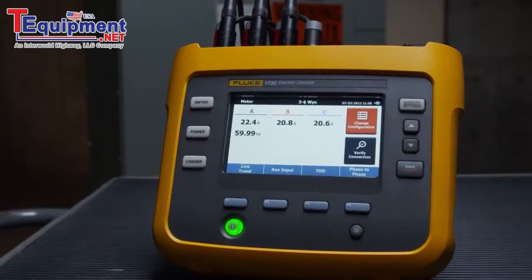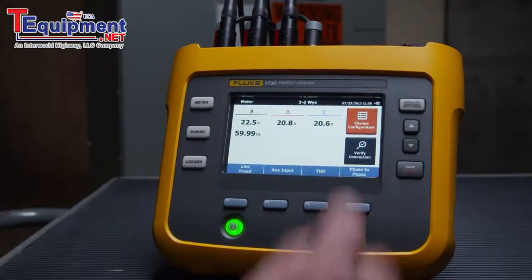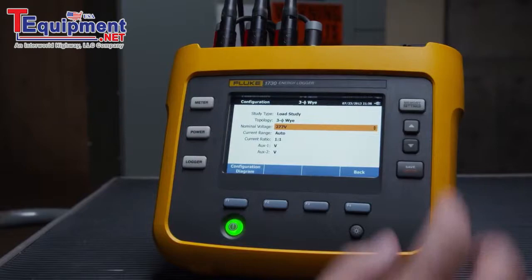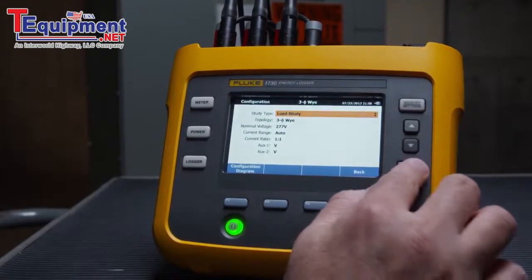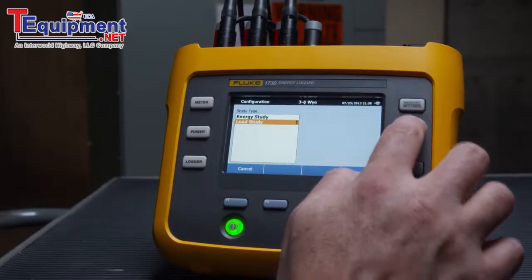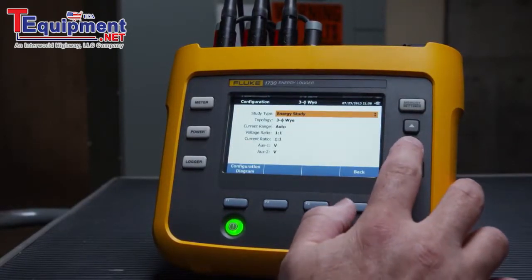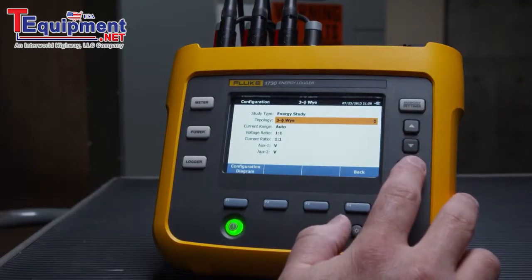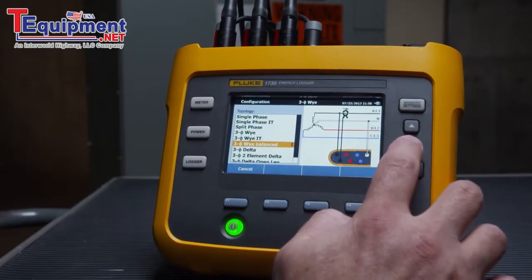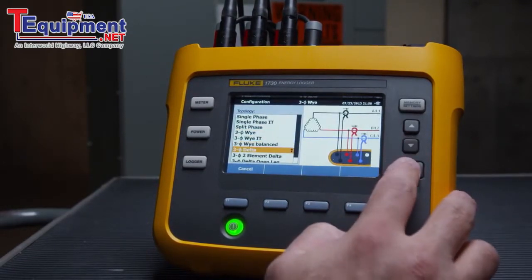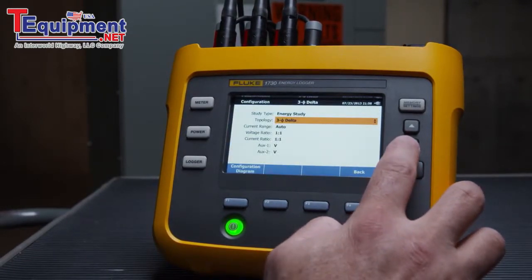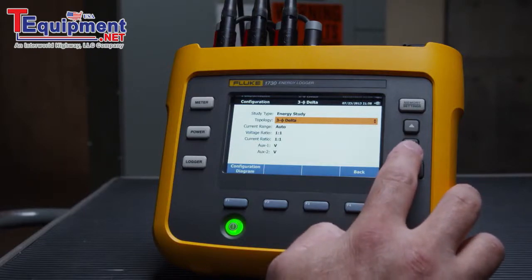To begin energy logging, start at the meter screen, select Change Configuration, and choose Energy Study under Study Type. Now choose Topology and select your circuit type from the list. Other settings, such as where the current and voltage transformers are installed, can be selected to ensure all measurements are shown correctly.